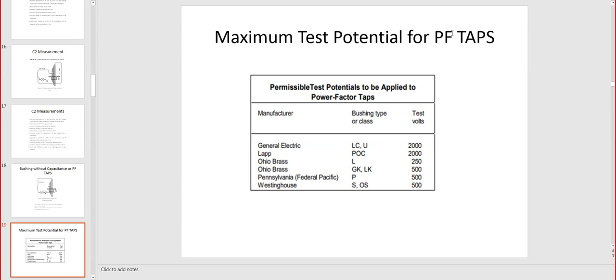Maximum test potential for PF power factor taps. So here we have the manufacturers: General Electric, Lapp, Ohio Brass, Pennsylvania, Federal Pacific, and Westinghouse. And then subtypes, what kind of bushings we have from these manufacturers, LC, U, L, and so on. And then the test voltage that we were talking about for measuring the leakage from the tap to the ground is here. So this is the test voltage for General Electric, and Lapp is 2000 volts, and then Ohio Brass depends on which type, is 250 or 500, and then Pennsylvania and Federal Pacific 500, and Westinghouse 500. So those are the voltages that will be applied in order to measure the leakage current through the bushing and the capacitance and power factor.